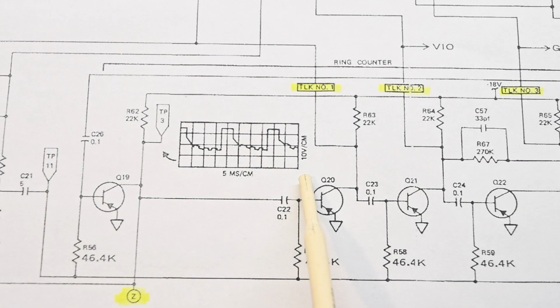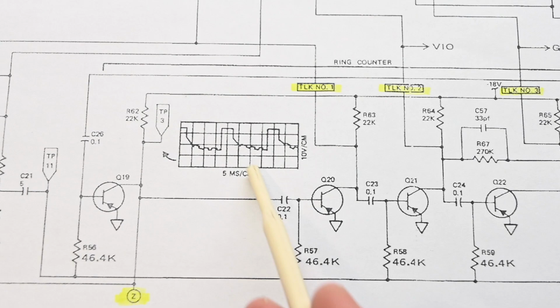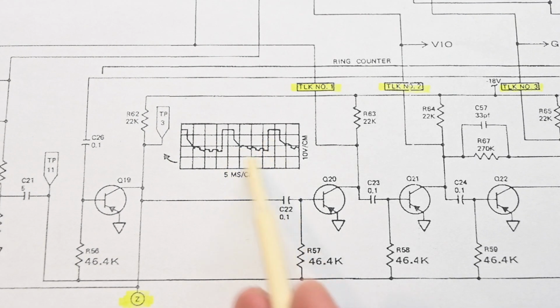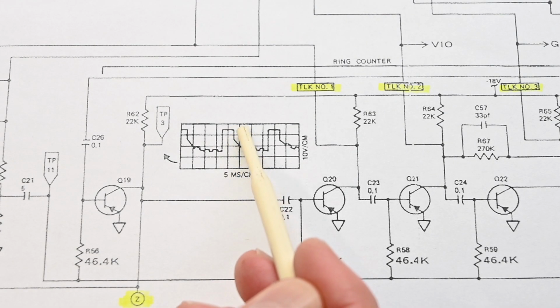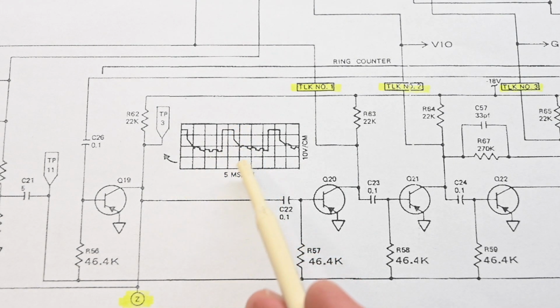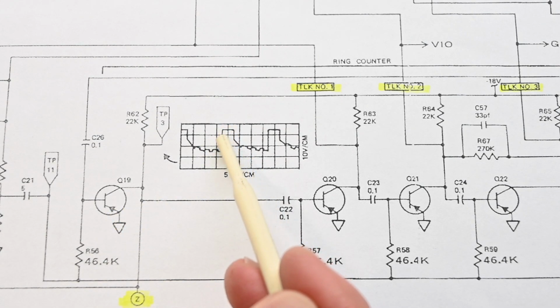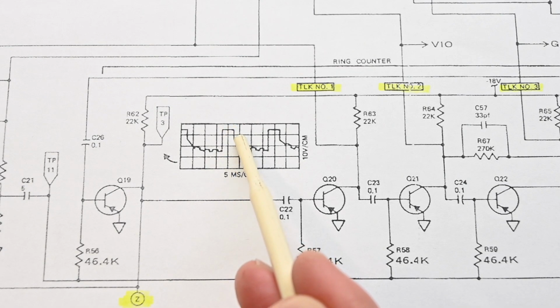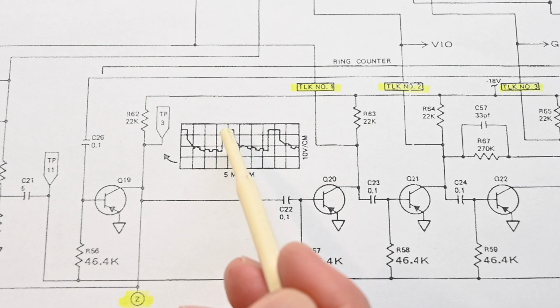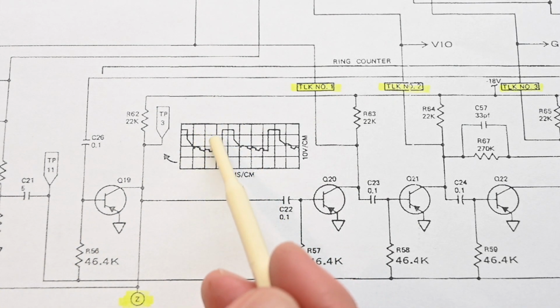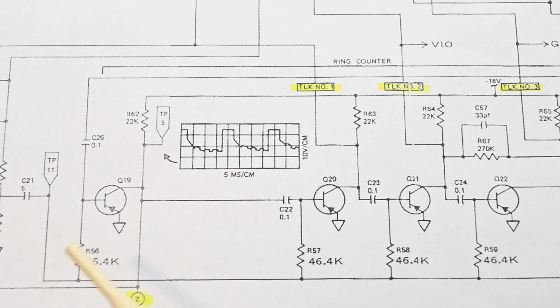So I'll set the oscilloscope up the same way, 10 volts on the vertical and 5 milliseconds on the horizontal. So you'll get the same reading, the same look on the oscilloscope. So you're supposed to have about a 10 volt step on this falling side right here. And we do get that. It looks perfectly fine. There's not supposed to be a notch in the center, so it comes up, it's flat, and comes down, and repeats again. And when it's working correctly, there is no notch, but check out the notch when it isn't working correctly. It's absolutely horrible. So that's a big sign of a problem.